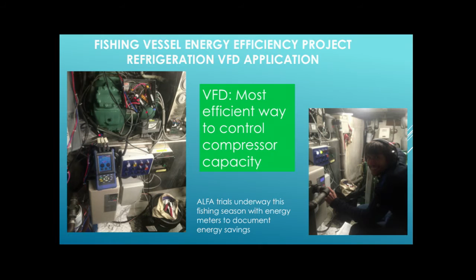What we do is we put a variable frequency drive on the unit so it slows way down to reduce the capacity. On the one that we had it on, we were up about 10 kW to run the machine. We slowed it down and went to 4 or 5 kW at the low end. We're doing trials underway. We're actually putting the meters on board to physically document the savings from using this technology.